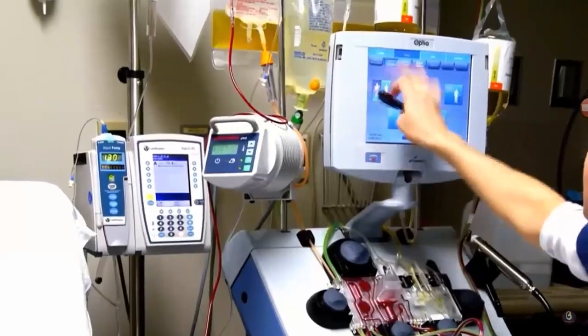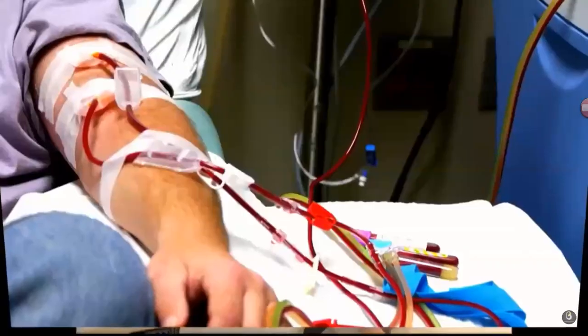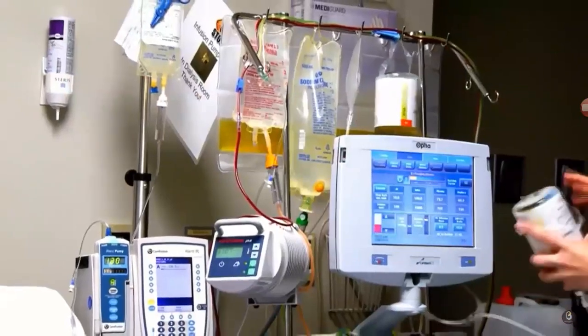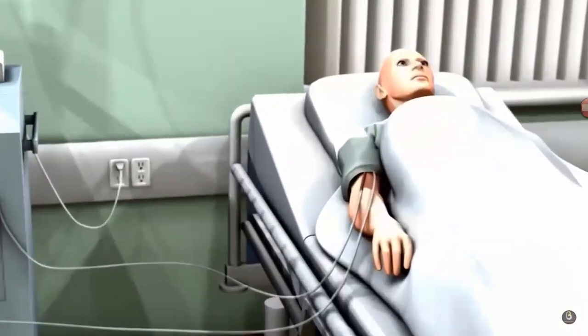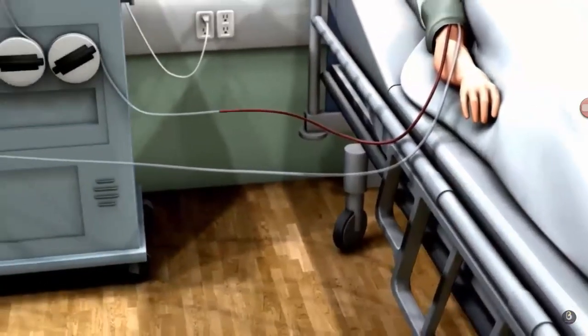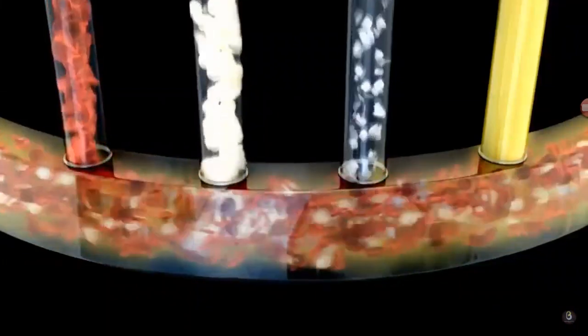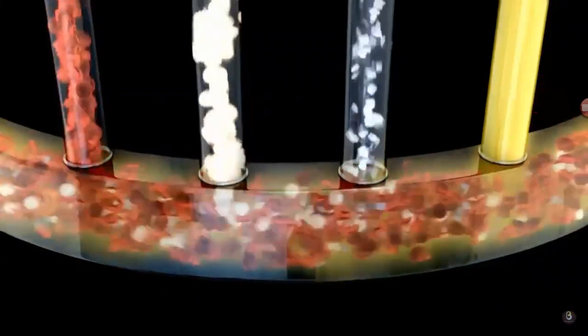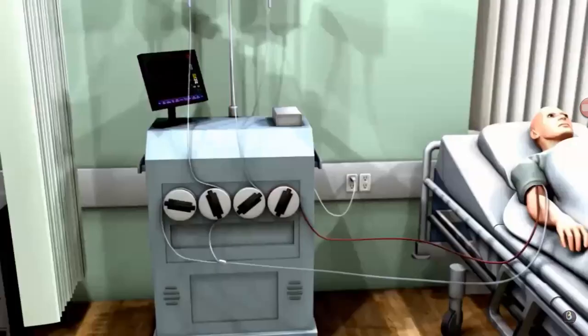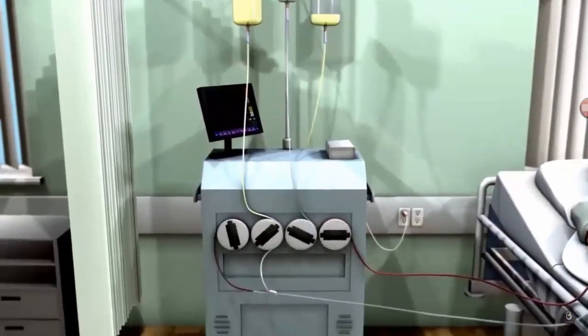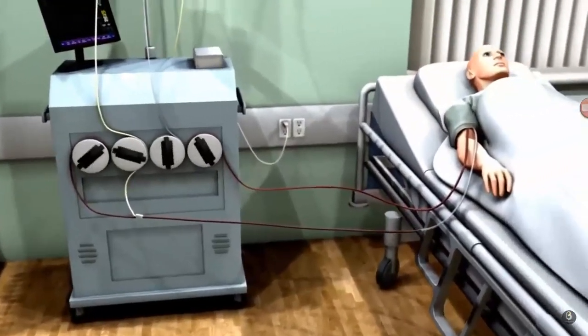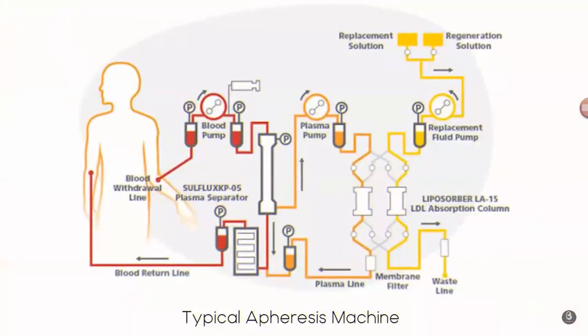How does the apheresis machine work? Apheresis units incorporate polyvinyl tubing that draws blood from the patient and moves it through centrifuges and/or filters to separate blood products. The blood is then returned to the patient via tubing or is collected in bags, often suspended from a pole, for donation or disposal. A display and control panel allow the operator to program the unit and view progress and/or alerts. Safety features include pressure sensors, ultrasonic air bubble detectors, optical fluid level detectors, and dry heat fluid warmers. The warmers prevent hypothermia caused by infusing low temperature fluids. The unit may have wheels or it may be placed on a cart.